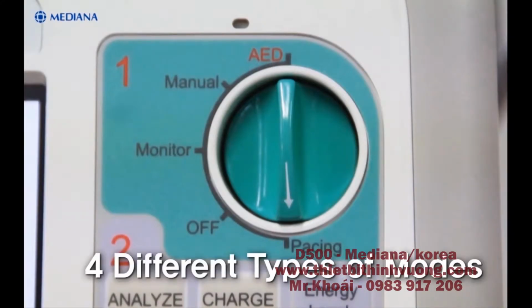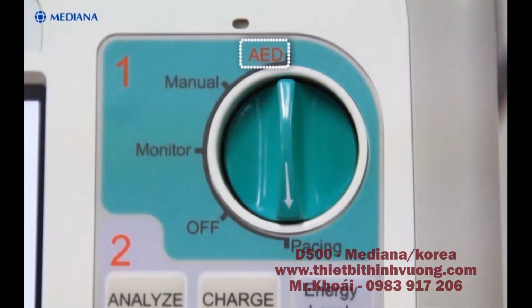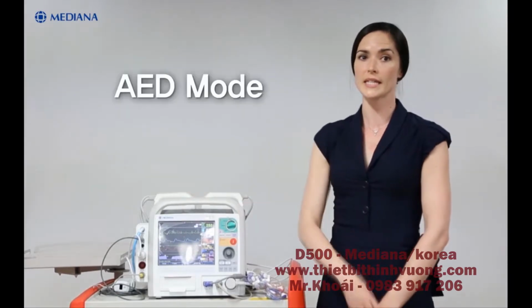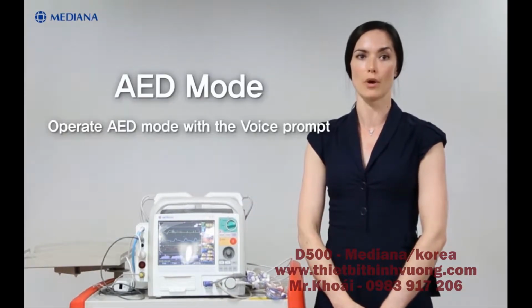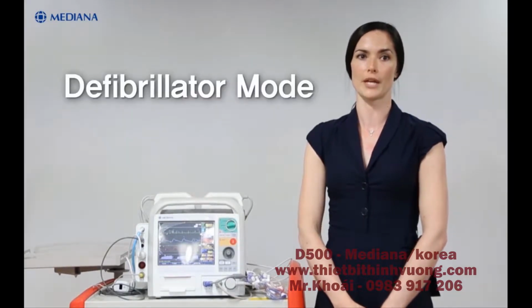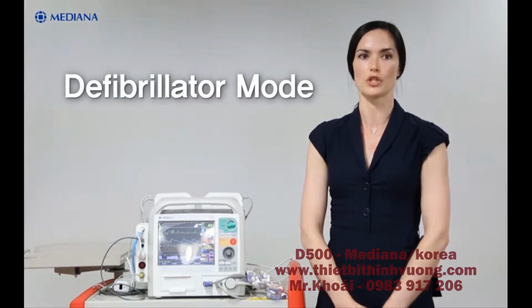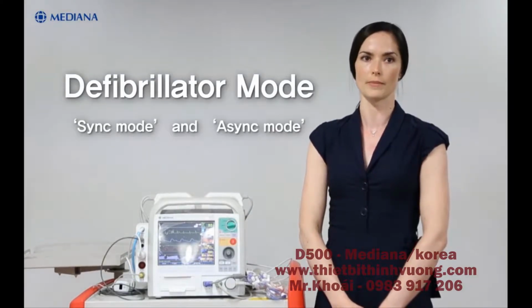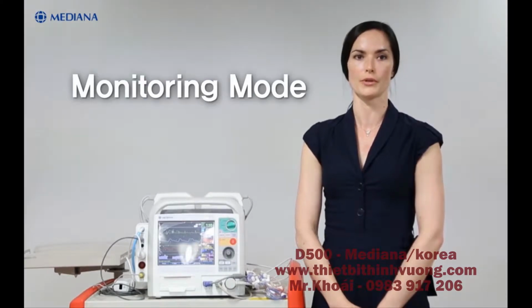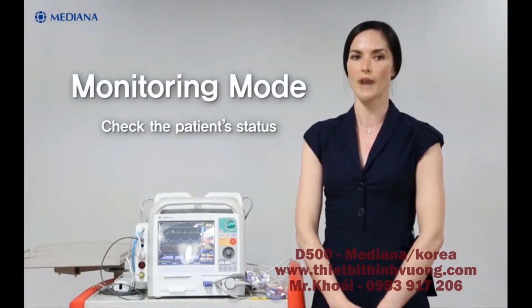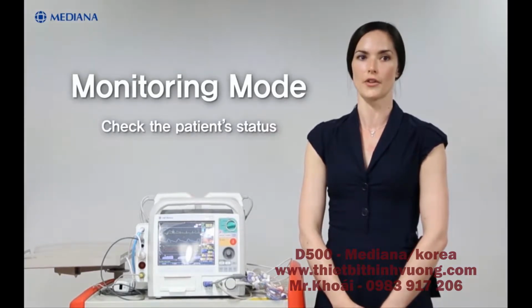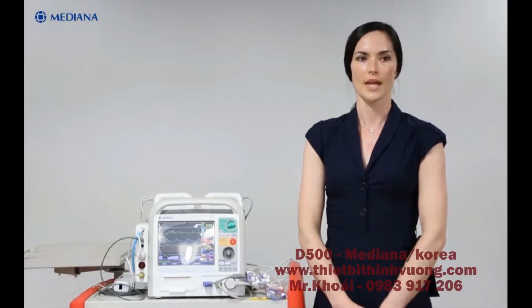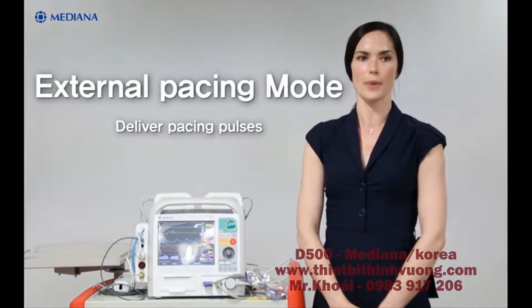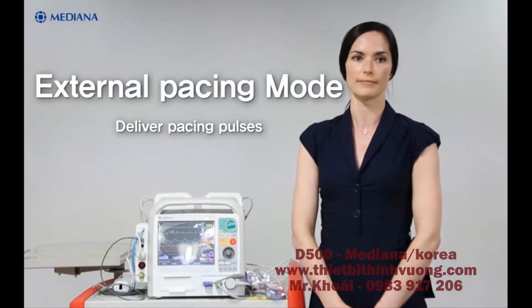D500 has 4 different types of modes: manual mode, AED mode, monitoring mode, and external pacing mode. And we can select the desired mode by rotating this mode select knob. In AED mode, you can operate AED mode with the voice prompt. In defibrillator mode, you can operate the defibrillation with 2 types, sync mode and async mode. D500 has a monitoring mode, so you can check the patient's status with 3, 5, or 12 lead ECG and other vital signs, depending on your options. And external pacing mode is used to deliver pacing pulses in either sync mode or async mode.